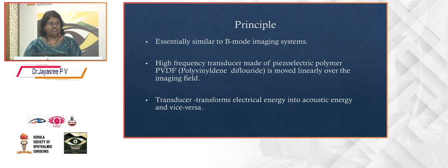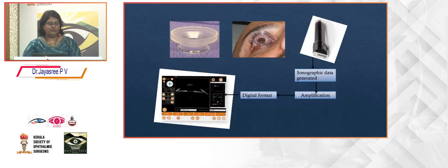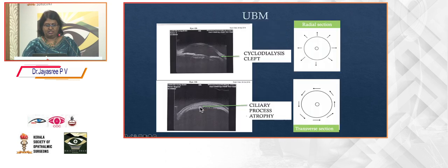A high frequency transducer, which is made of piezoelectric polymer, is moved linearly over the imaging field, and the transducer transforms the electrical energy into acoustic energy and vice versa. So this is how the parts are there. This is the water bath, the water immersion that is used, which is kept onto the eye like this, and after filling the water, this transducer is kept and imaging is done.